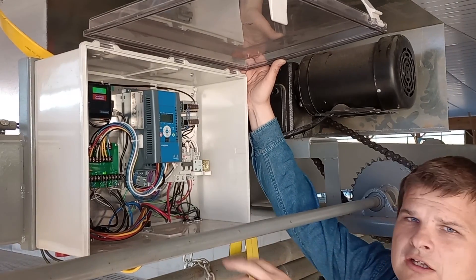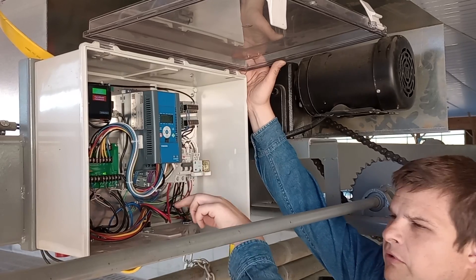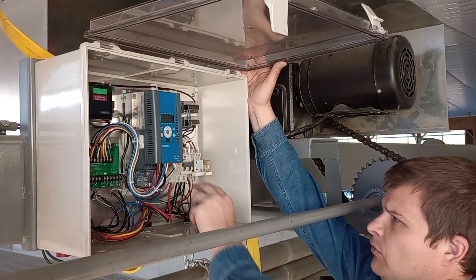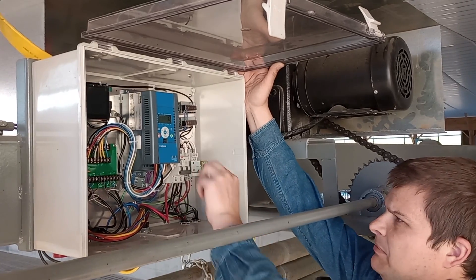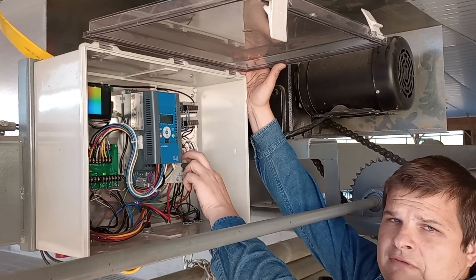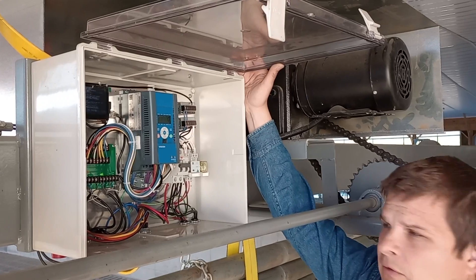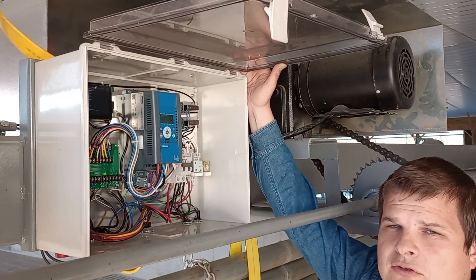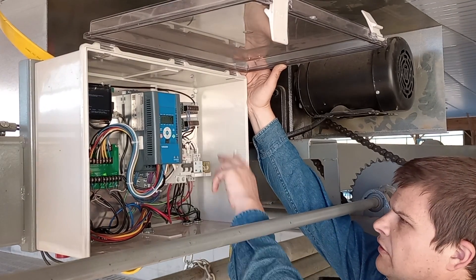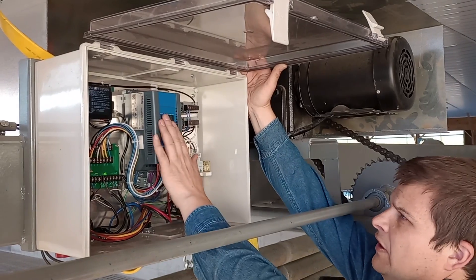The Hoover crowd gate: power comes into this breaker at the bottom and goes out the top. To turn the power off to the unit, just snap it down; snap it back up to turn it on. If it's not operating, use a voltmeter and check between these two terminals for 240 volts single phase — all the crowd gates are 240 volt single phase — to make sure power is present.